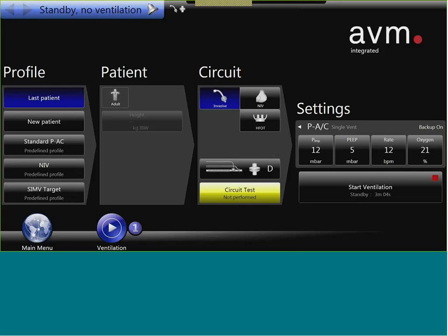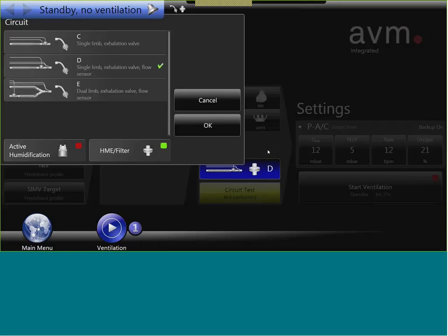Is the selection, active humidification, and HME/Filter new? What changes with the bellavista? This is currently only available in the US, so internationally we don't have that selection. It's just that the flow sensor, for better accuracy, if the flow sensor knows that the air is already warmed up with active humidification, we have now a better accuracy during active humidification.